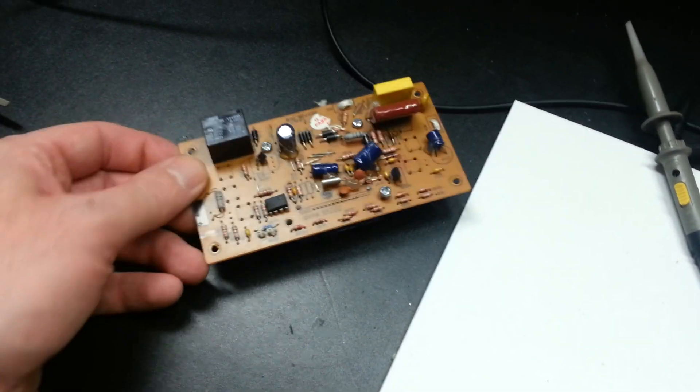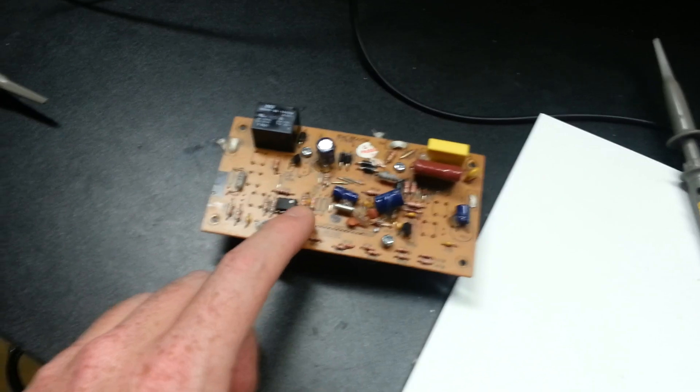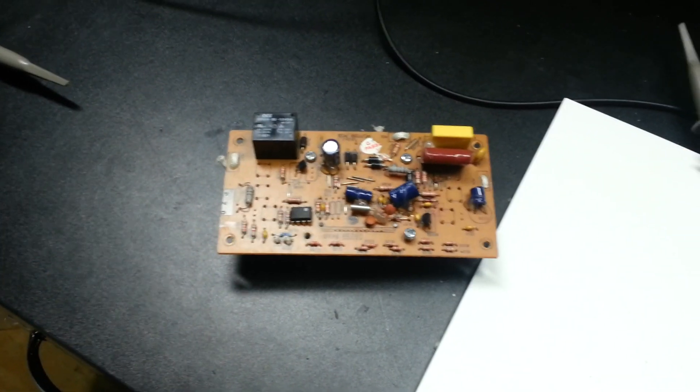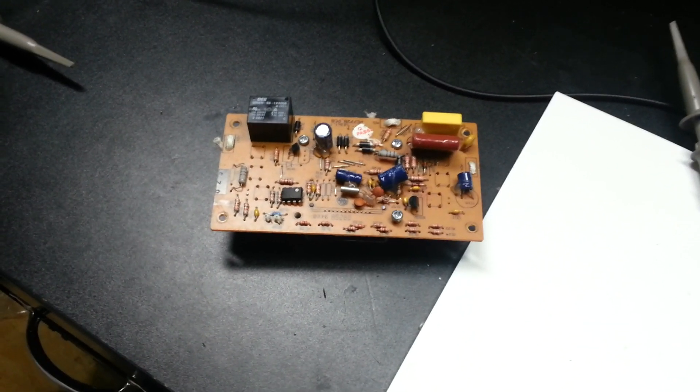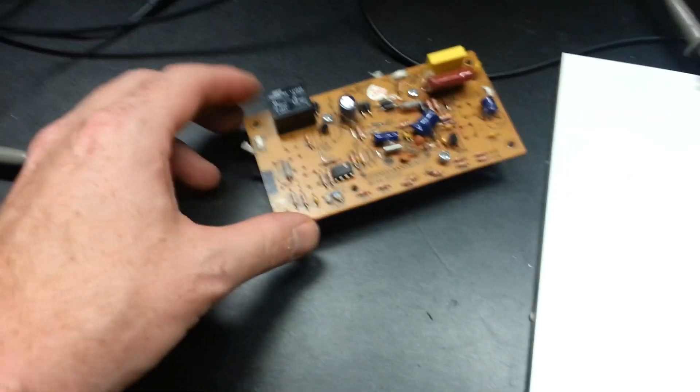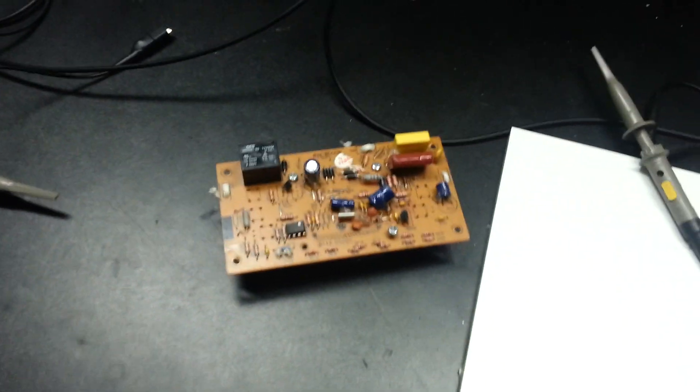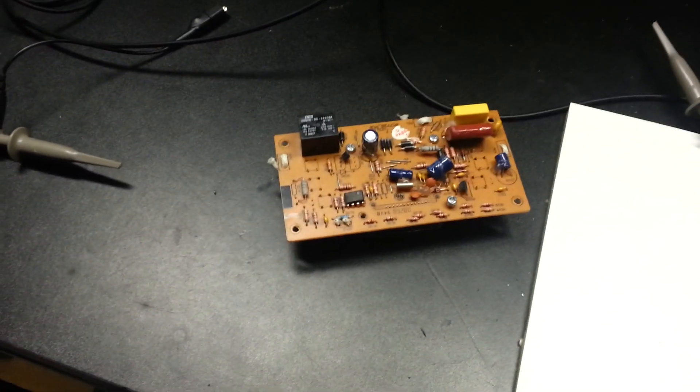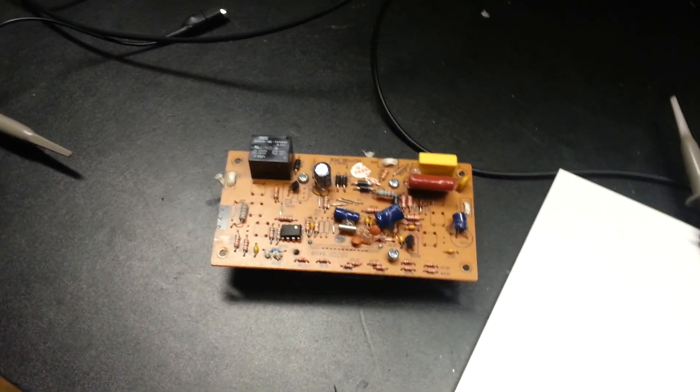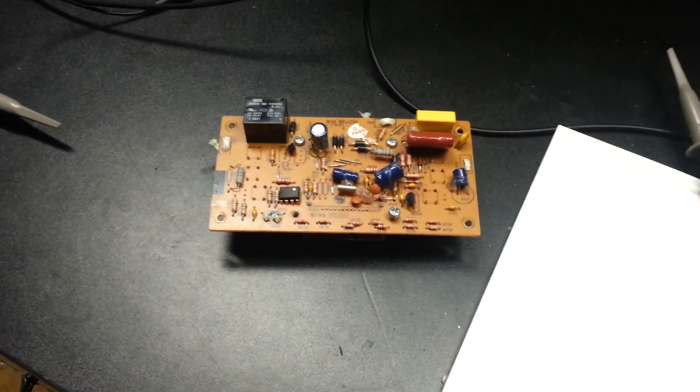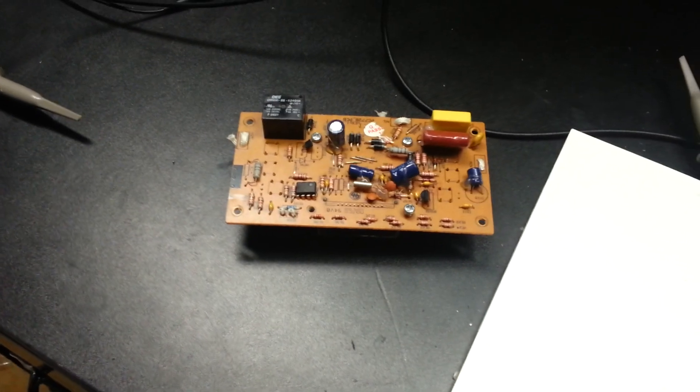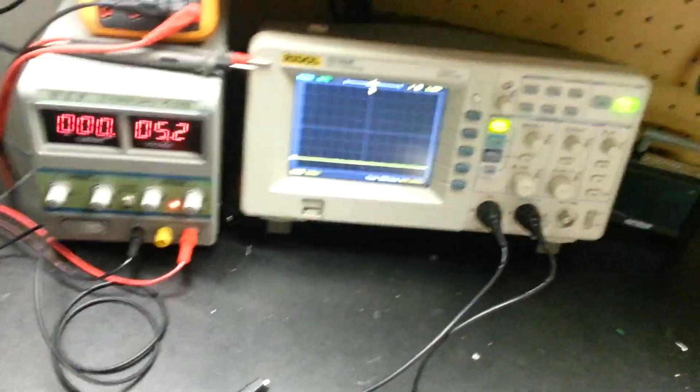This thing's plugged into mains power. If you touch a point on this circuit, your feet are on ground potentially. You have now made a reference path to ground through you, extremely dangerous. What you get is an isolation transformer. Your component being tested would plug into the secondary side of the transformer. The primary side would be plugged to mains power. There is no ground reference then for the component you're working on. You're completely isolated from ground, therefore keeping you far more safe.